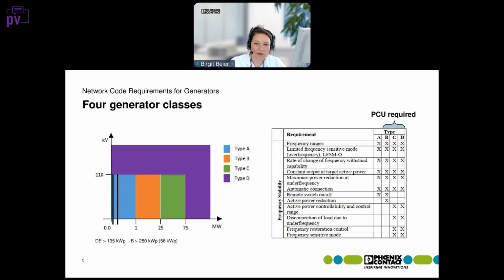Now I want to have a look at the 4 generator classes in the NCRFG. You can see on the left-hand side, it really depends on the size of the power plant. With the growing size of the power plant from A to D, the requirements will grow as well. You can see it in the list here. From type B, a PCU is required. But every member state can, of course, be stricter than the network code requirements for generators. For example, in Germany there's a limit at 135 kilowatt peak, and in Belgium it's 250 kilowatt peak. And my colleague told me that this will soon be lowered to 56 kilowatt peak. Okay, so everywhere from type B, there's a PCU required.